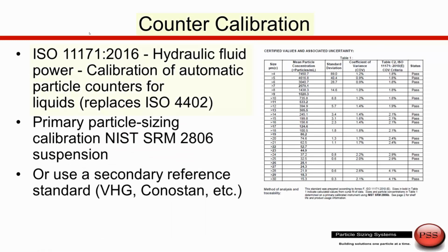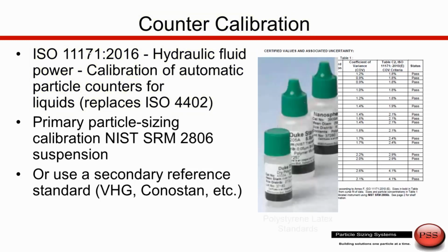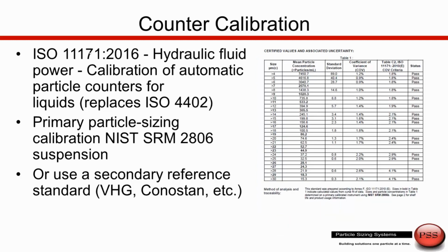The next ISO standard we'll talk about is ISO 11171, and this specifically addresses the calibration of the sensor for the liquid particle counters used for this test. For most other industries and most other applications, we calibrate these instruments using polystyrene latex standards, which are very narrow standards at very specific sizes. But in the contamination business, we typically use contaminants that are closer to real-world contaminants, and these contaminants are dispersed in a clean hydraulic fluid. What happens with these standards is there's a contaminant mixed in oil, and most people reference the primary standard, which is NIST SRM 2806. And NIST SRM 2806 has known contaminants in particles per ml at various size ranges. This standard is the primary standard.